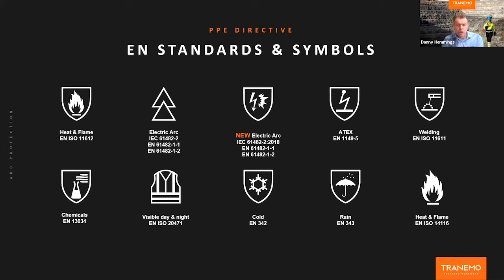There are a few things I want to cover today that will be quite new in terms of knowledge on electric arc. The first one of those, you'll see there are 2 symbols relating to electric arc. There's the symbol that's got the two triangles, one on top of the other, and then there's a symbol next to it which has a lightning strike going downwards with a pictogram of an explosion coming out from it. This is really the difference between the standards that we've been working to and the standards that we're now going forward with, in particular the new standard, IEC 61482-2 2018, which is a revised standard which we'll touch on shortly.